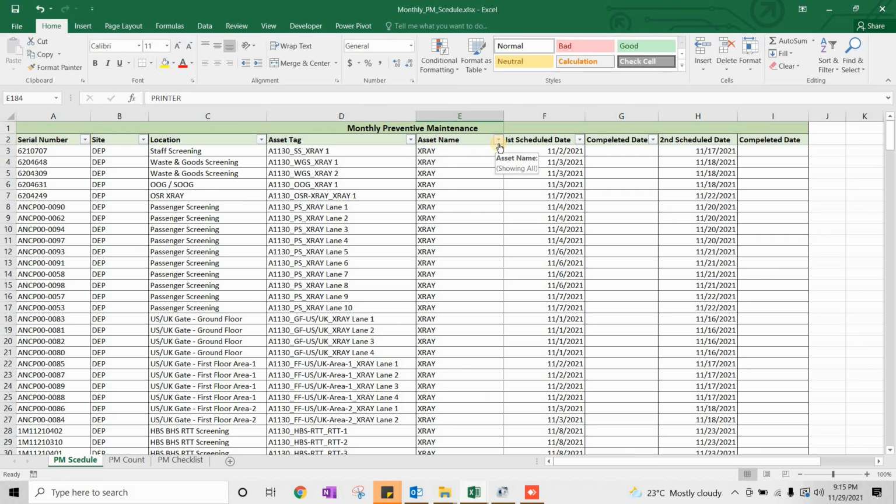If one guy worked on that, one guy is enough, and the duration will be 2 hours for that. And if it takes much more time, because you are fixing something in the report, or fixing something with the machine, you have to increase the time accordingly, based on how much time it will take to fix that machine or do the PM. If there is any breakdown during the PM, any time which is added will be included in that report. But the generic time is 2 hours for that machine.